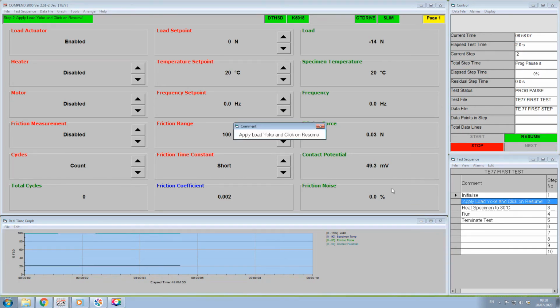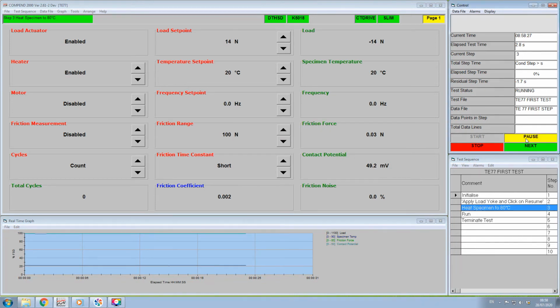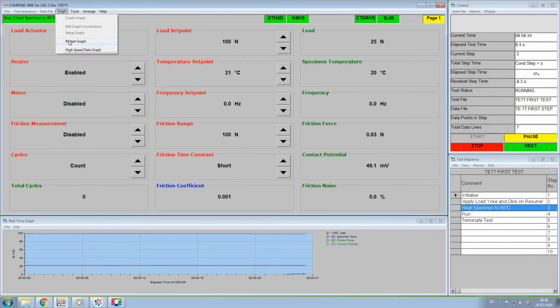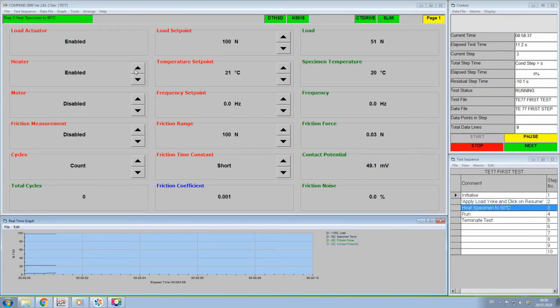The test is at the pause we programmed in step 2, and we have the prompt message on the screen. Once we are satisfied that the prompted action is complete, press resume and the test sequence will continue. It's a good time to restart the real-time graph. The live buttons on the control panel allow the operator to override the test sequence and either pause or stop the test. The next button causes the test sequence to jump from the current step to the next step.